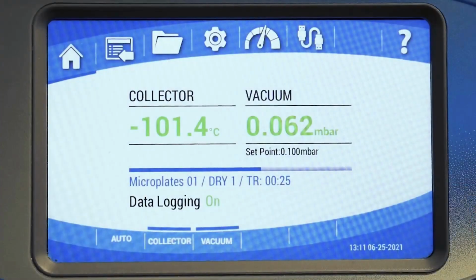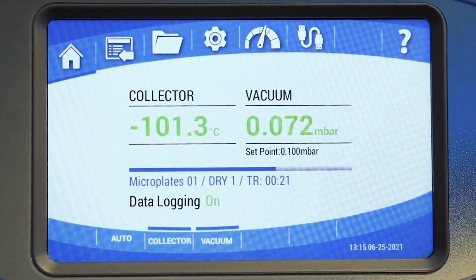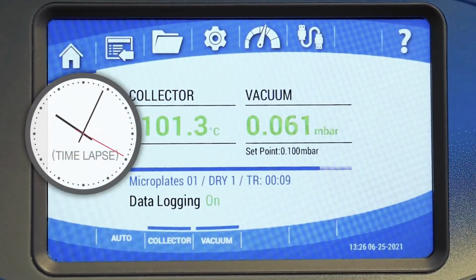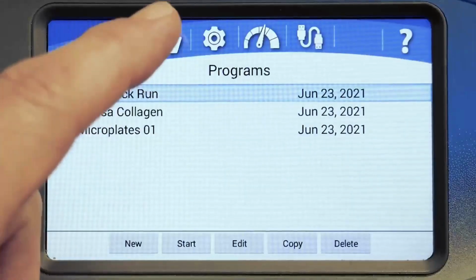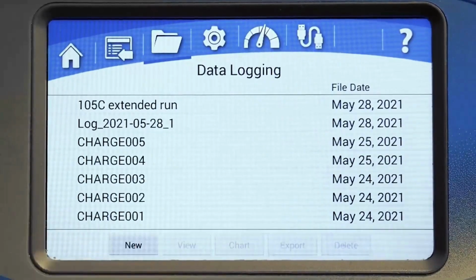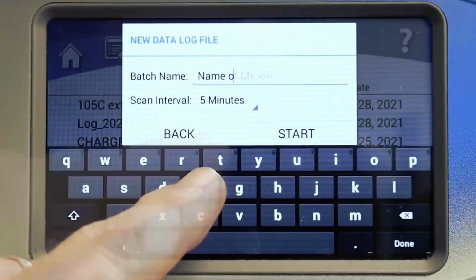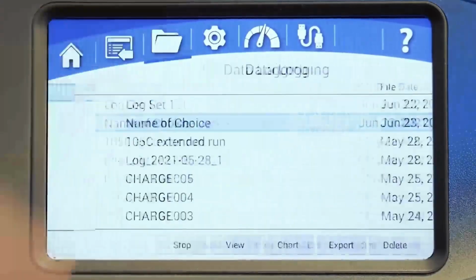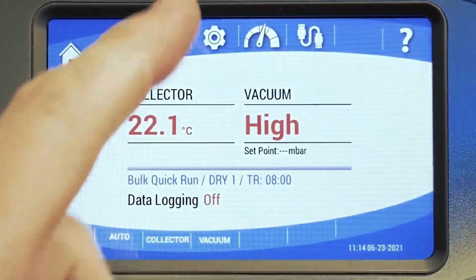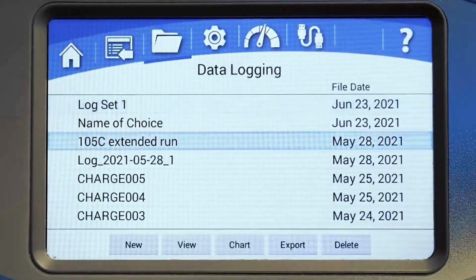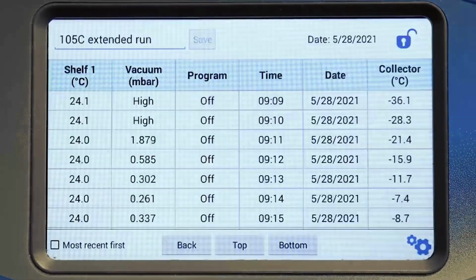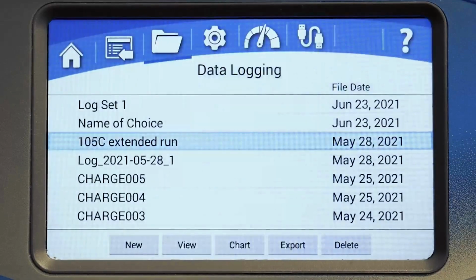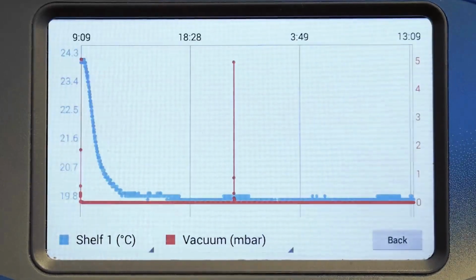The status of a program that is running can be easily seen with a quick glance at this progress bar on the home screen. The time remaining in the program is also displayed. On the data logging screen, use the New button to start logging your freeze-dry run data. You can stop logging data at any time. Use Data View to review a saved data log. You can chart data from one temperature sensor and one vacuum sensor at a time.